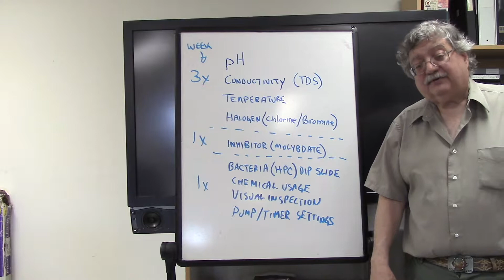test for the bacteria level in the cooling tower. That's called HPC, heterotrophic plate count. You do that with a dip slide like this device: take a sample of water from an appropriate location, dip it in, shake it off, put it back, and place it into a device that keeps it at the same temperature for 2 days. After 2 days you take it out and read it. We'll cover how that test is performed later, but you have to do it once a week.